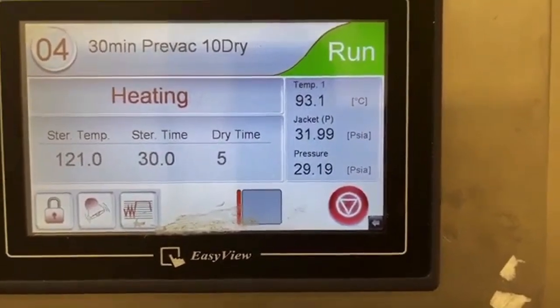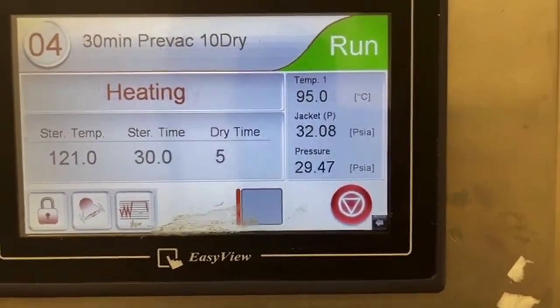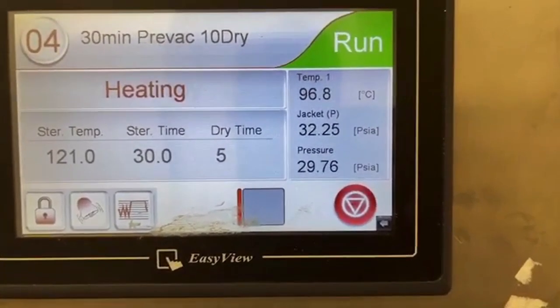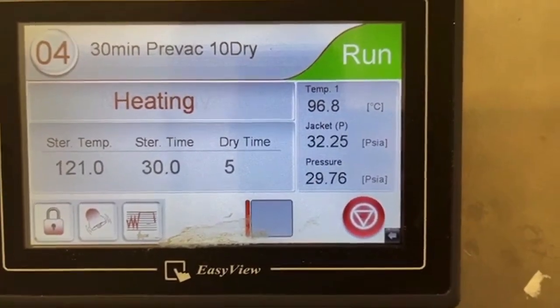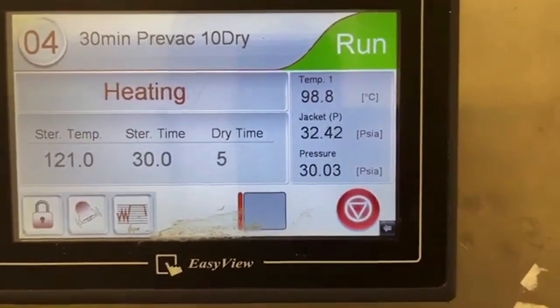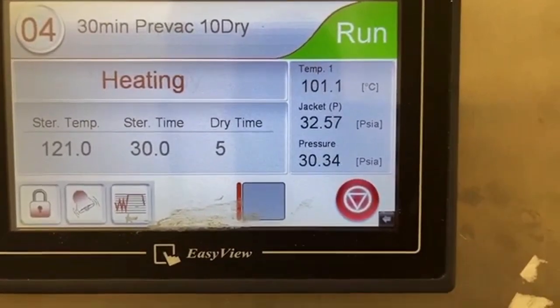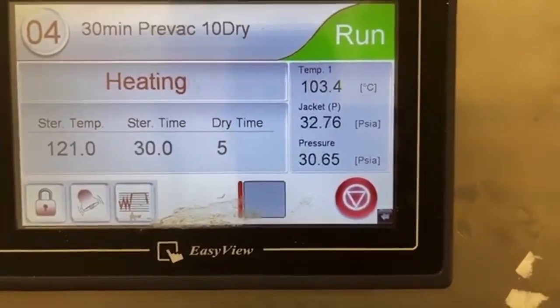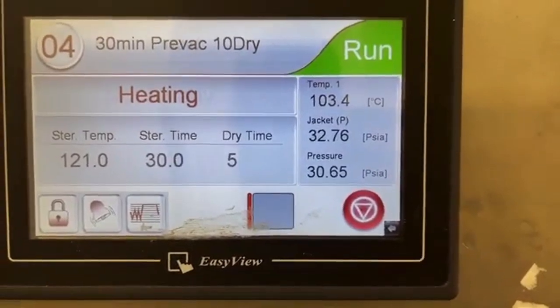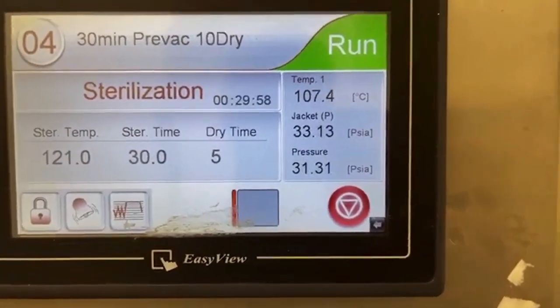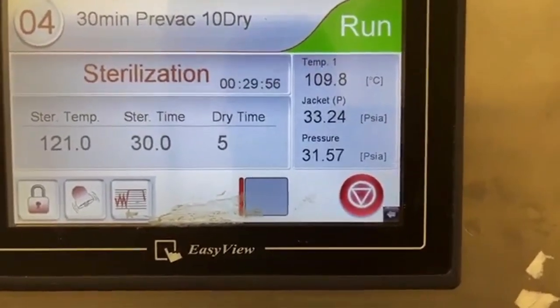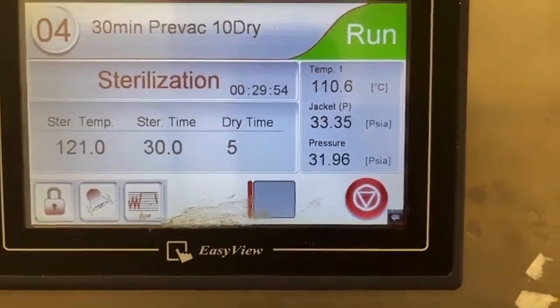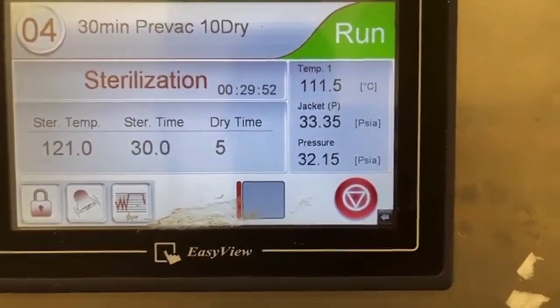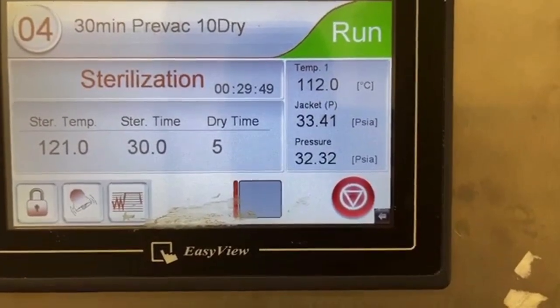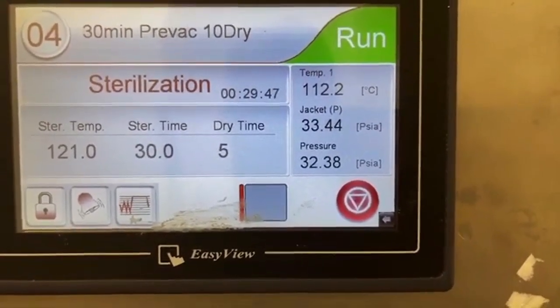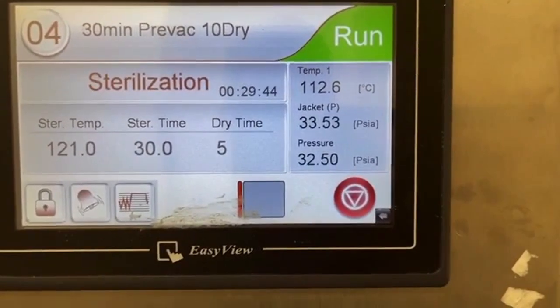And by the time this goes into sterilization, our temperature inside the middle of that bag should be at sterilization temperature or pretty close to it. So I'm going to hang in there for a little bit and wait for it to kick over into sterilization, and let's see what the difference is. Okay, our chamber is now at 122, and let's see how long it takes before our meat achieves the 121 that we need.